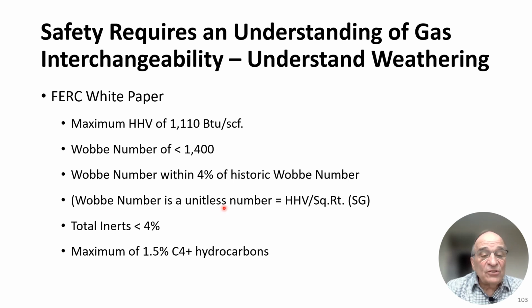And the Wobbe number is a unitless number that is nothing more than a higher heating value divided by the square root of the specific gravity of the gas. And the specific gravity of the gas is nothing more than the density of the gas at STP divided by the density of air at STP. The total amount of inerts in the gas being sent out must be less than 4%, and the maximum amount of heavy hydrocarbons, that's C4 plus hydrocarbons, must be 1.5%, no more than that 1.5%.